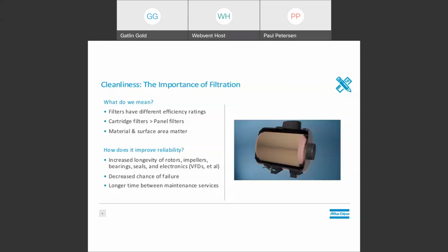There's a nice seal. However, most blowers start and stop at least weekly, sometimes daily, sometimes several times a day. When the blower stops, dust, pollen, and any other particles may fall off that filter and into the cracks in the housing between the panel filter and the housing itself. When that blower starts up again, it's very easy for the blower to suck those particles into the compression chamber before the filter makes that seal again through that vacuum. Those particles can bypass the panel filter.